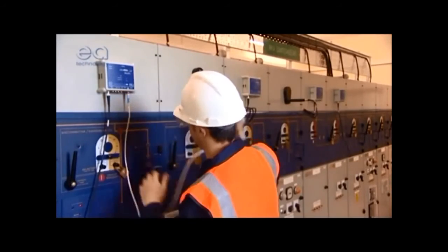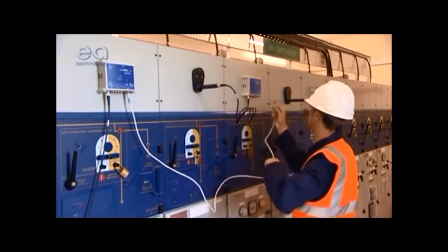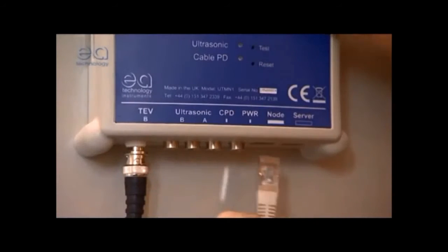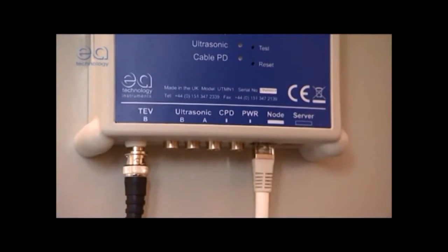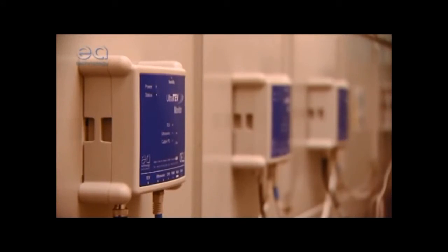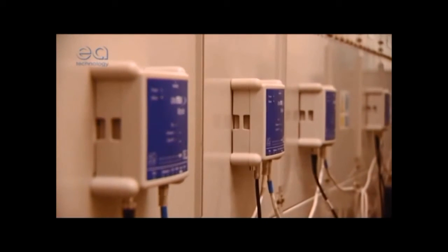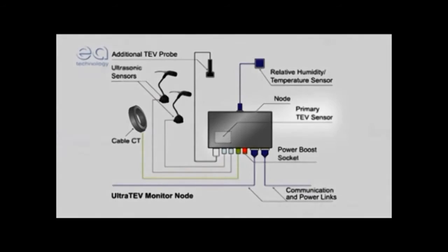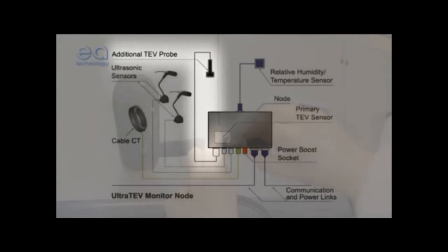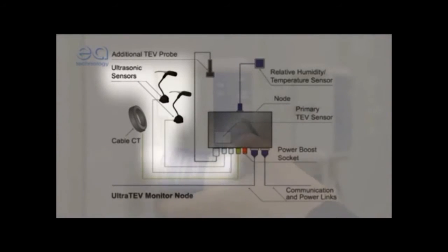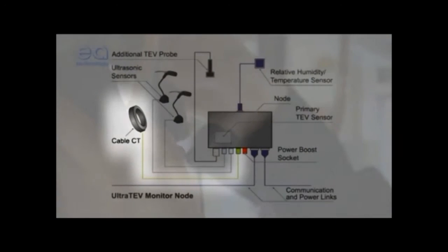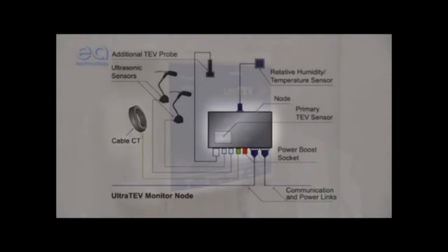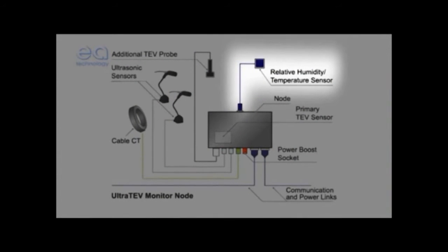Installation and configuration are both very simple, because it uses EA Technologies' new UltraBus networking solution, which carries both data and power over a single cable. Each measurement node supports five types of sensor: a built-in TEV sensor plus additional plug-in TEV probe, an ultrasonic microphone plus additional contact probe, a plug-in radio frequency sensor for measuring PD in cables, a built-in temperature contact sensor, and a plug-in ambient temperature and relative humidity sensor.